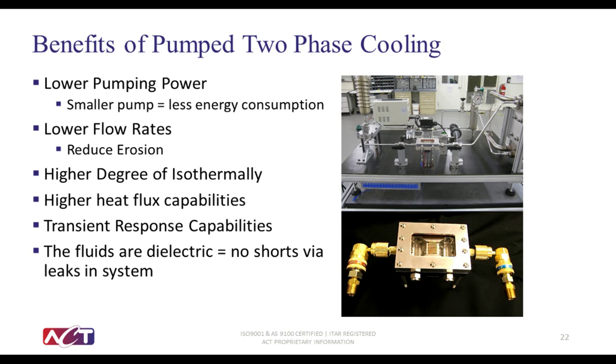So what are the benefits of pump two-phase cooling, especially compared to pump single-phase cooling? First, it requires lower pumping power. A smaller pump means less energy consumption. We'll look at some numbers that support that in the following slide. P2P also uses lower flow rates, which can reduce erosion. Pump two-phase cooling offers a higher degree of isothermality. If we can maintain boiling across the evaporator surface, we can also maintain a uniform temperature there.